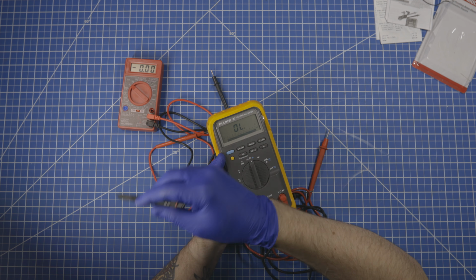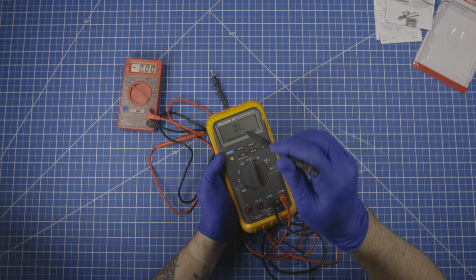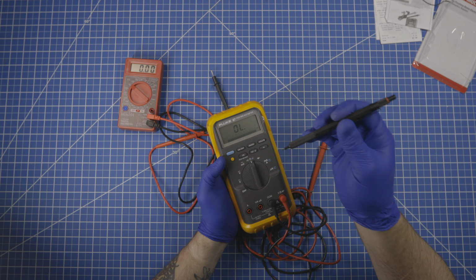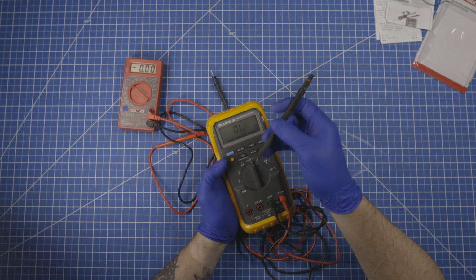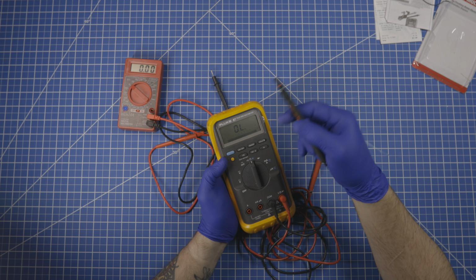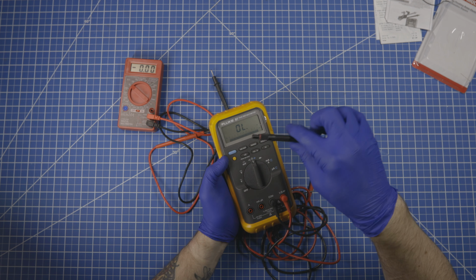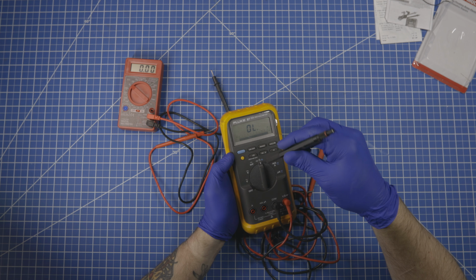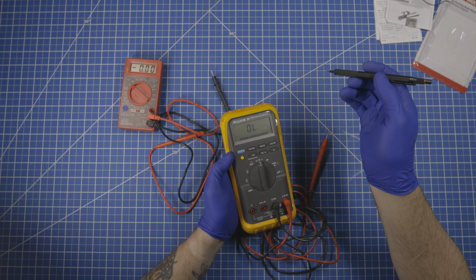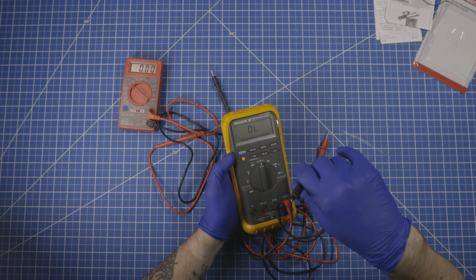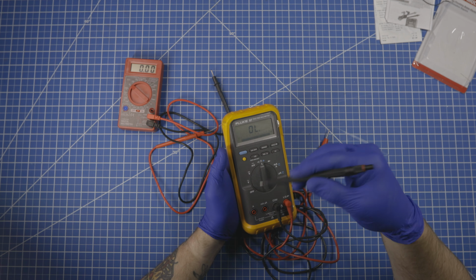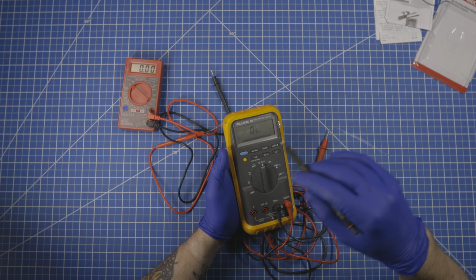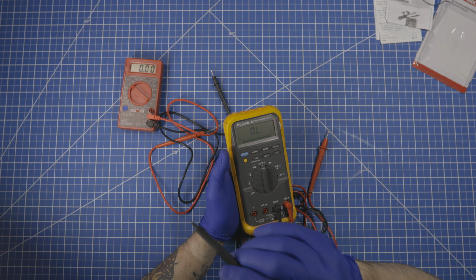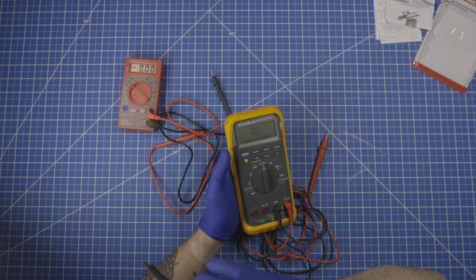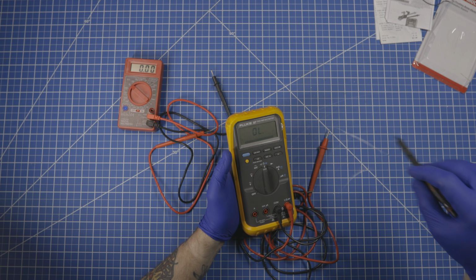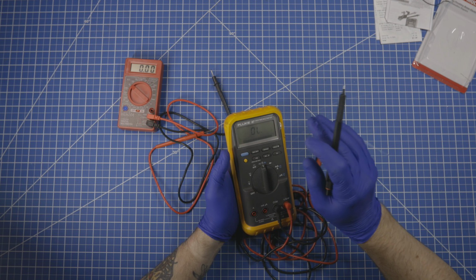This takes that non-sinusoidal AC waveform and calculates the equivalent direct current version of that measurement. When you're dealing with things like a motor controller, an electronic ballast for old style tube fluorescent lights, or HVAC motor controls, the waveform isn't smooth. It's squared off or has weird little humps instead of a smooth sinusoidal wave. This meter does all that work for you.